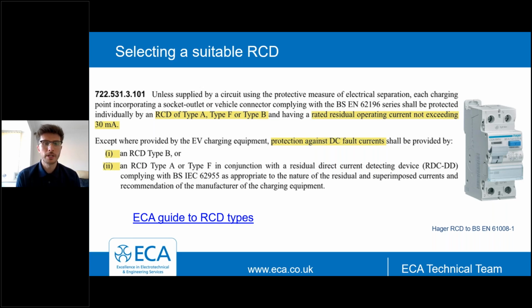So we know now we need to do either a type A, type F, or type B. How do you know which one to select for your EV charge point equipment? Well, again, this is where conversations with your manufacturers are going to be key, consulting that manufacturer's data to confirm which device is required for the specific EV charging equipment.